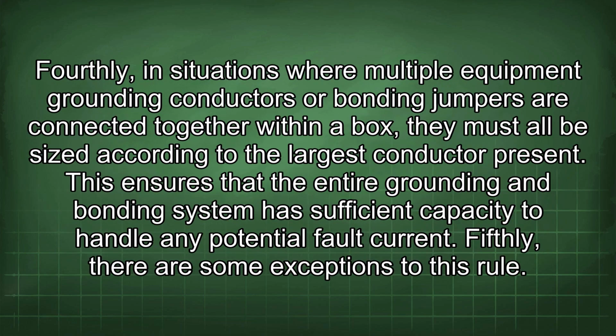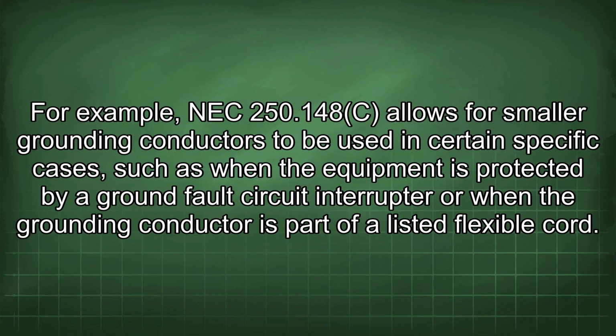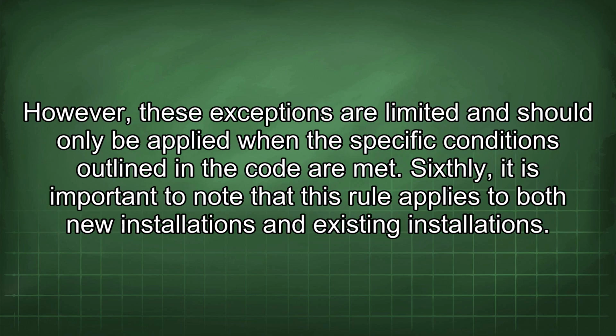Fourthly, in situations where multiple equipment grounding conductors or bonding jumpers are connected together within a box, they must all be sized according to the largest conductor present. This ensures that the entire grounding and bonding system has sufficient capacity to handle any potential fault current. Fifthly, there are some exceptions to this rule. For example, NEC 250.148c allows for smaller grounding conductors to be used in certain specific cases, such as when the equipment is protected by a ground fault circuit interrupter or when the grounding conductor is part of a listed flexible cord. However, these exceptions are limited and should only be applied when the specific conditions outlined in the code are met.